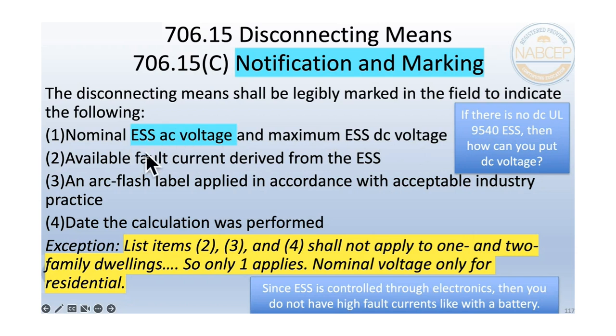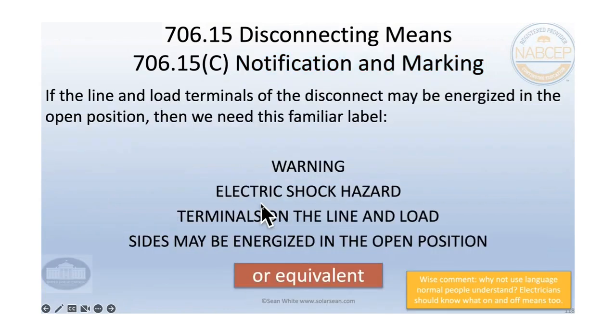The fault current, if you have something bigger than a 1 and 2 family dwelling, you would just have to get that from the manufacturer. And the same would go with the arc flash label and the date the calculation was performed. A lot of this stuff sounds like 480 battery type of stuff too, where they probably took it out of there. The date the calculation was performed. Like if you have a lead acid battery, over time the short circuit current will get less as the battery wears out.